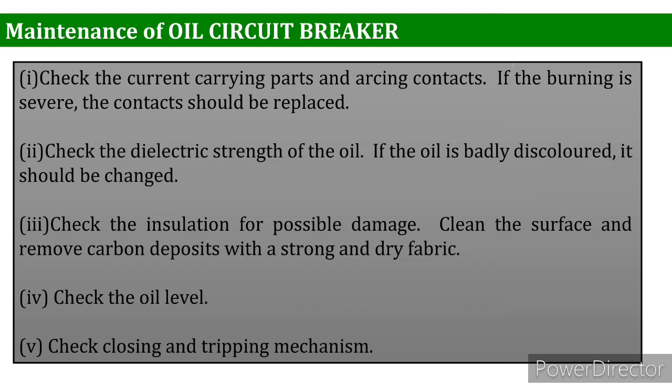The third one, we have to check the insulation for possible damage, clean the surface and remove carbon deposits with a strong and dry fabric. So the insulation must be protected, and the carbon deposit must be cleaned with a strong dry fabric, so the contamination of the oil should be avoided. The fourth one is to check the oil level. Oil level is very important. If the oil level increases, it is also not good, and if the oil level decreases, this is also alarming. So we have a complete check on the oil level to avoid any damage.